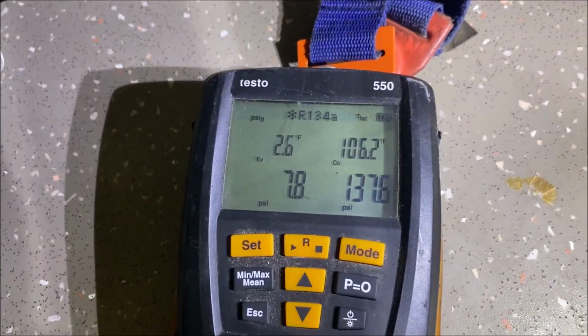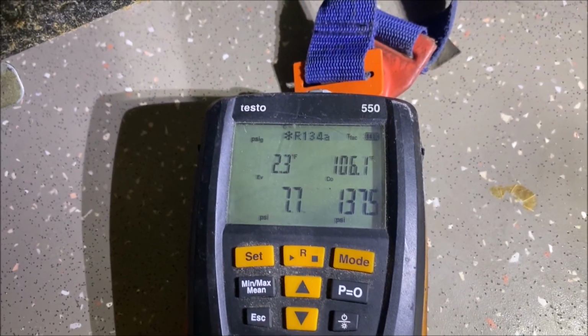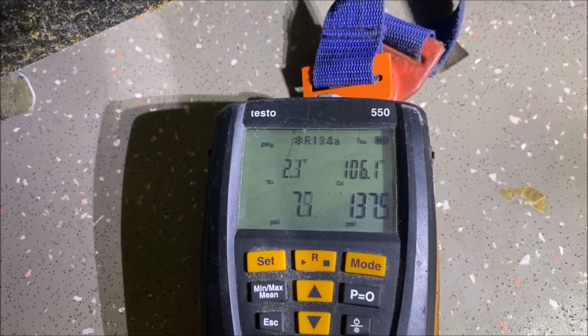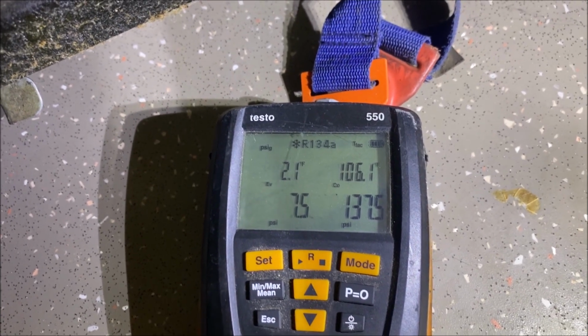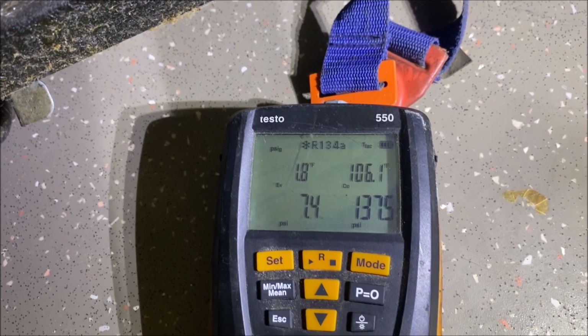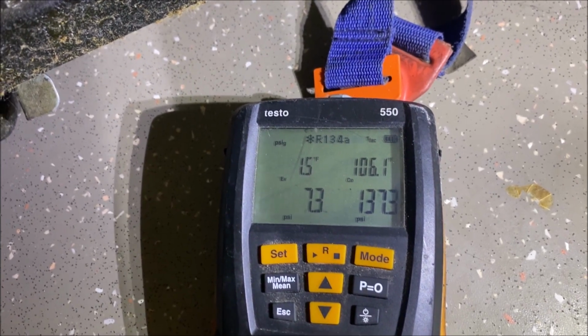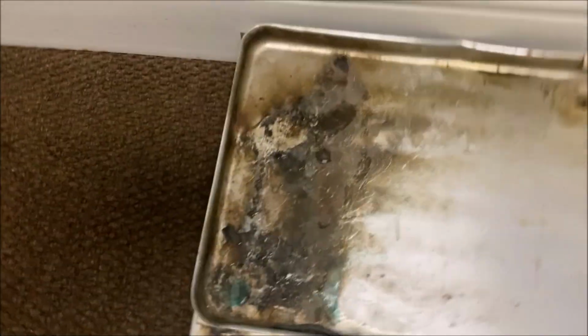All right, so I've added some refrigerant. You can see our pressures have now come up. They're 8 and 138. They're not exactly what I want, but it tells me now that we're not restricted in the system and we're hunting down a leak. So let's go do a leak test and see if we can hunt this leak down.